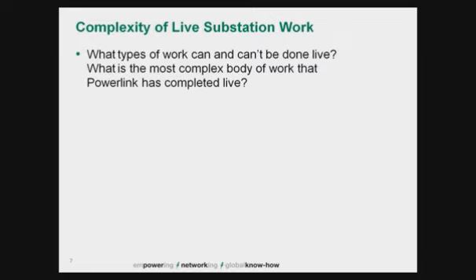Actually, I shouldn't say limitless; there are some limitations. Things like power transformers, connecting power transformers, we don't work on those. We have limits as to what we can connect up with our different devices from a capacitance point of view. And one other thing that we don't do here at Powerlink, it can be done, but we have chosen not to go down the path, and that's welding live. We have an issue: do we train experienced live substation operators to be welders, or do we train welders to be live substation operators? It just gets a little bit too complicated, even though it can be done.